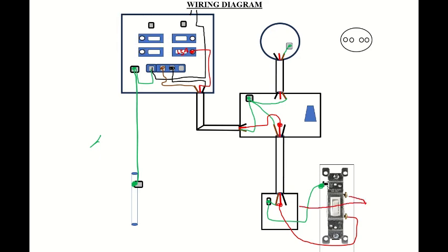And in this case, we'll connect it to the black. Now, the reason why we have black here is because a sheathed cable generally carries red, black, and an uninsulated solid strand earth wire, or it has blue, brown, and the same uninsulated. Right, so that is the reason why we have a black here. Now, if you are using trunking or conduit, then you could use another red wire.